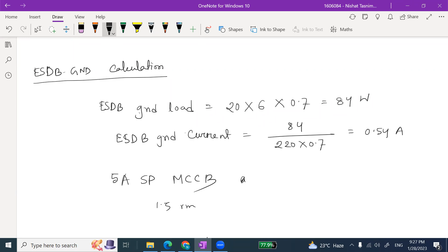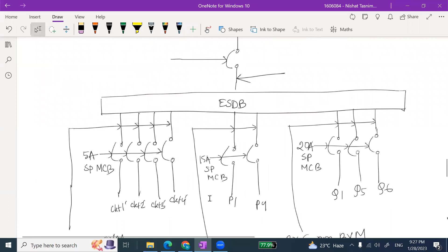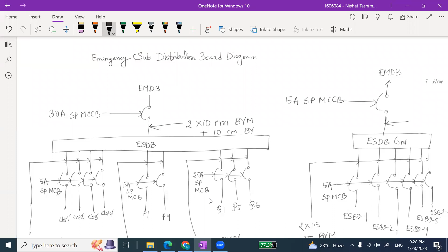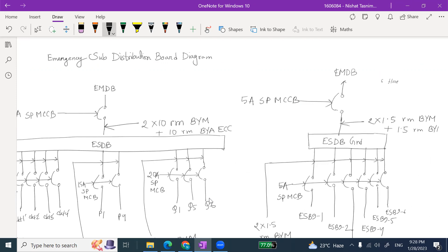ESDB. So here we got 30 ampere SP MCCB, and as for ESDB ground the current value was really less, so we told you that we will use 5 ampere SP MCCB. And for this 30 ampere, we have seen that we need to use 10 RM cable. 2 into 10 RM BYM plus 10 RM BYA ECC. And for 5 ampere, we usually use 1.5 RM cable, right? 2 into 1.5 RM BYM plus 1.5 RM BYA ECC. So now our emergency subdistribution board diagram, ESDB diagram, is complete.